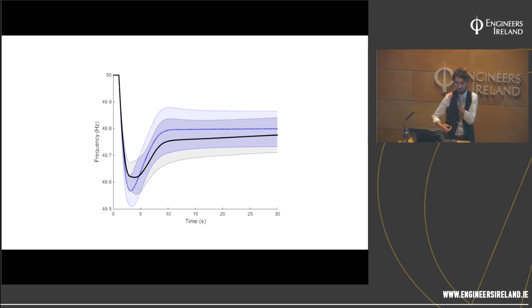But if it's tuned correctly, with any control device, it should help the system. Okay, and what I'm comparing here is, again, the full year scenario. So this is like 8,000 simulations each. The dashed blue line there is the mean system frequency without emulated inertial response from wind turbines, and the black is the mean system frequency of all those cases with a tuned emulated inertial response from wind. And the shaded boundary there is the standard deviation of the response, just to give you a feel for the rest of the simulations in terms of where we are moving.